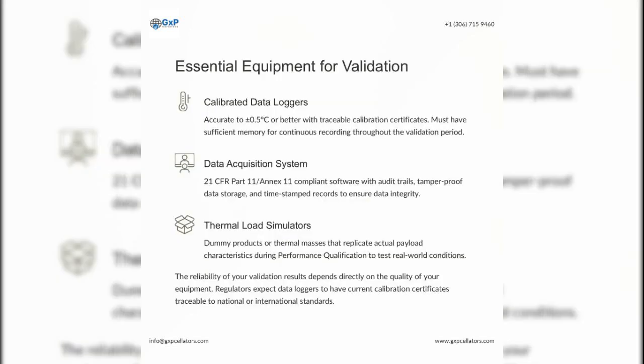Validation requires calibrated data loggers, data acquisition systems, and thermal load simulators. Data loggers must be accurate to plus or minus 0.5 degrees Celsius with traceable calibration certificates. Data acquisition systems ensure data integrity with audit trails and tamper-proof storage. Thermal load simulators replicate actual payload characteristics during performance qualification. The reliability of your validation results depends directly on the quality of your equipment. Regulators expect data loggers to have current calibration certificates traceable to national or international standards.